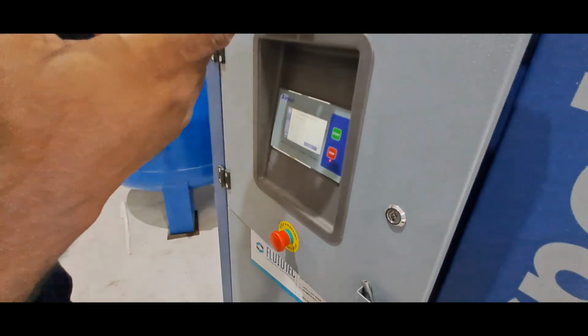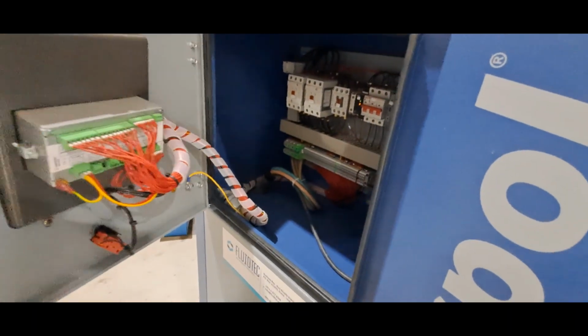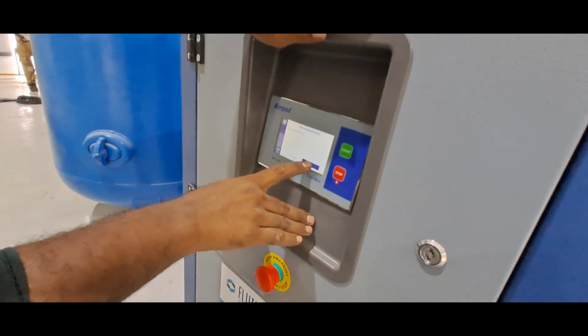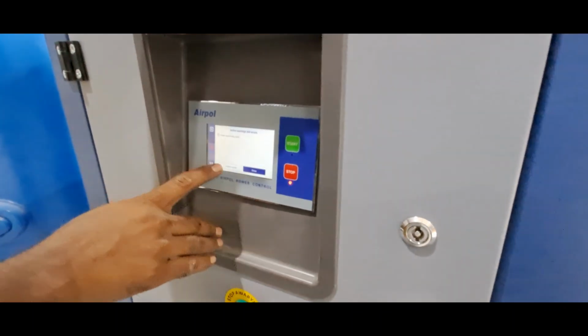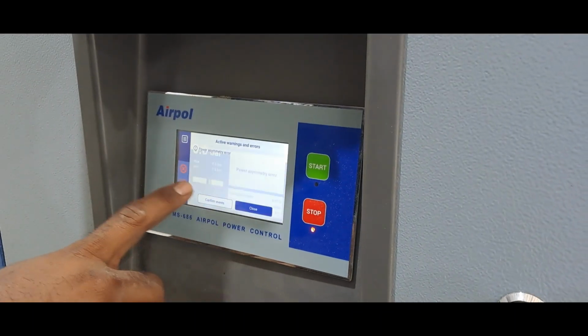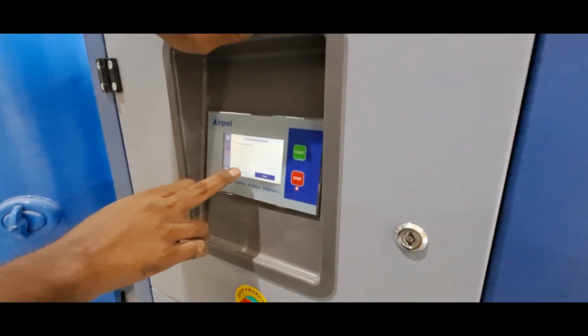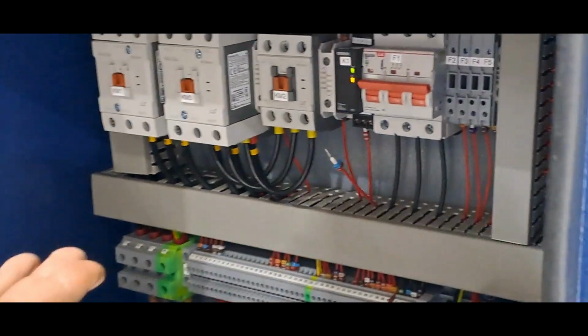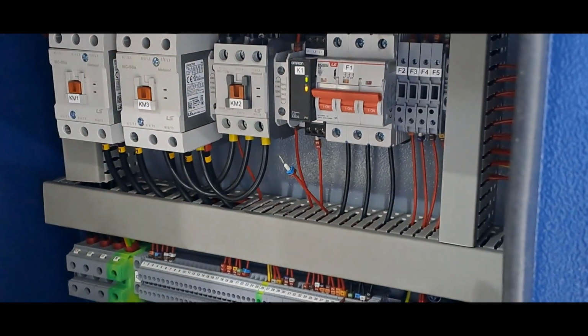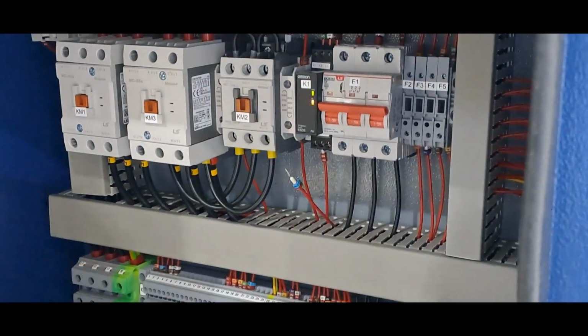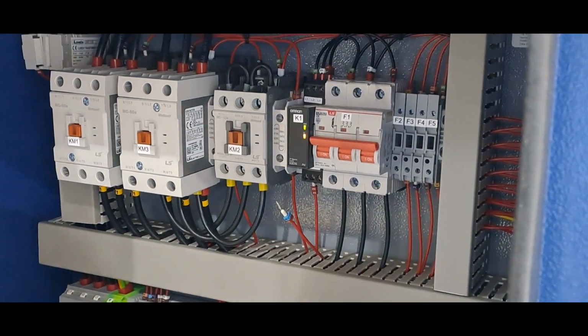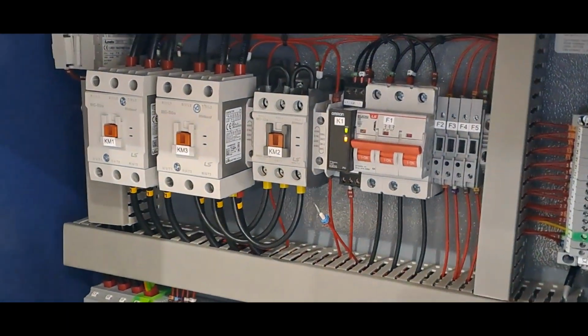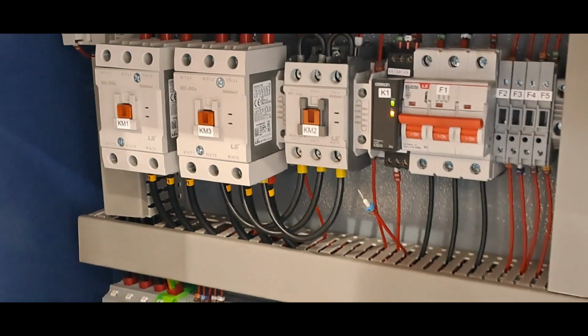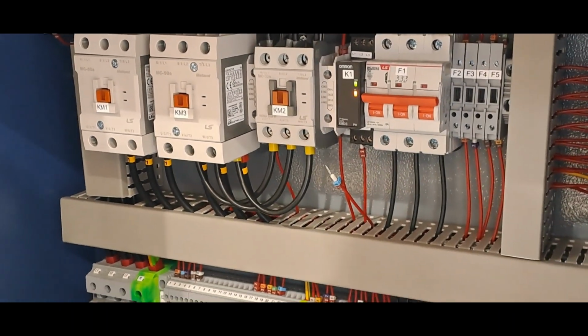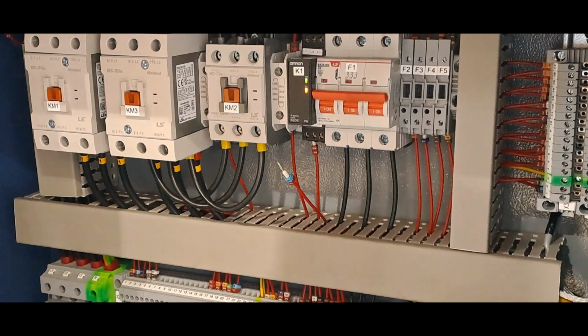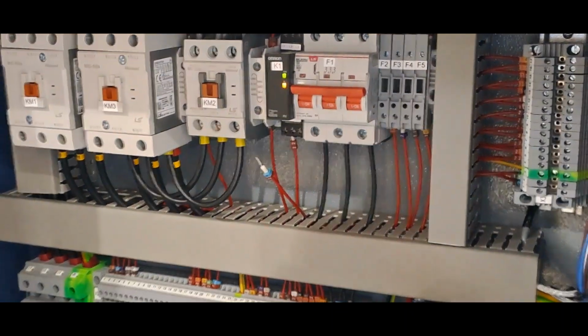So until we rectify that issue, this error will not get cleared. Okay. After confirming, we have to check whether there is a phase failure, where one phase is not coming, or if there is any voltage issue. If the voltage is less, this same power asymmetric error will come. This needs a minimum of 380 volts to run the motor. If the voltage is below 380, then this same error will come here.